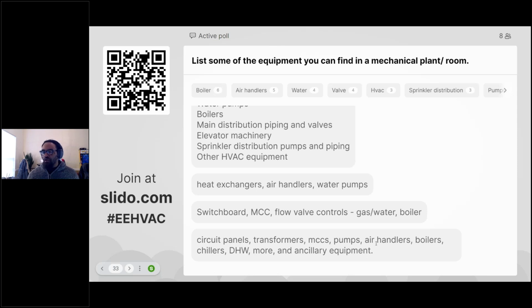or a facility that is extremely large, let's say it's maybe 40,000, 50,000 square feet, you'll have a main air handling system which will branch out throughout that entire facility. And you may even have that system have VAVs or VAV boxes embedded into that air handling system, so that way you have even more control over certain or specific zones depending upon your application. So yes, you definitely can find air handlers inside there. Well, at least your primary or main air handling system, ancillary equipment, and domestic hot water operations as well.